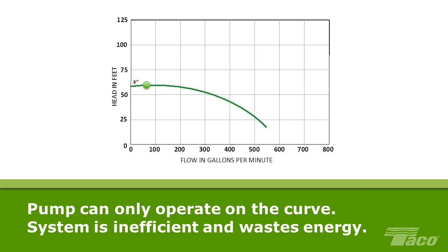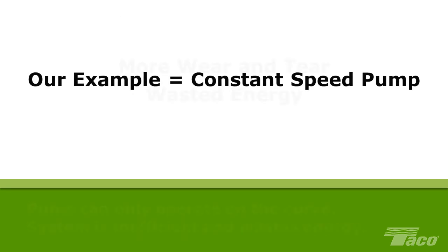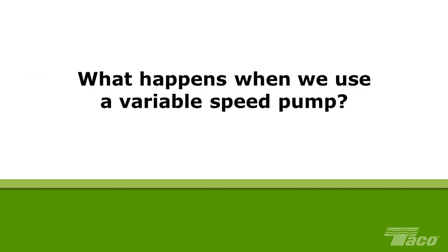In effect, the system must accommodate itself to pump performance since the pump can only provide an operating point on its curve. The result is system inefficiency and wasted energy. Remember, the pump in this example is a constant speed pump. What happens when we replace that pump with a variable speed pump?